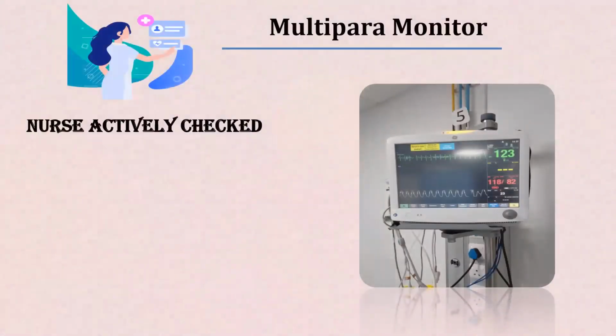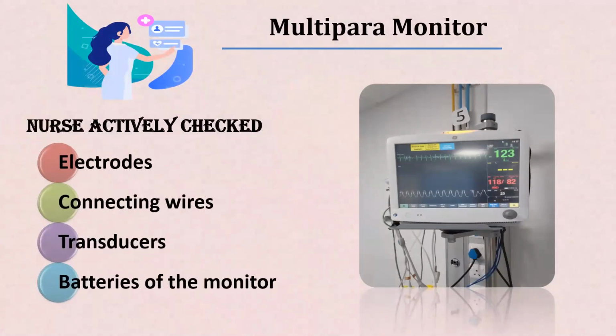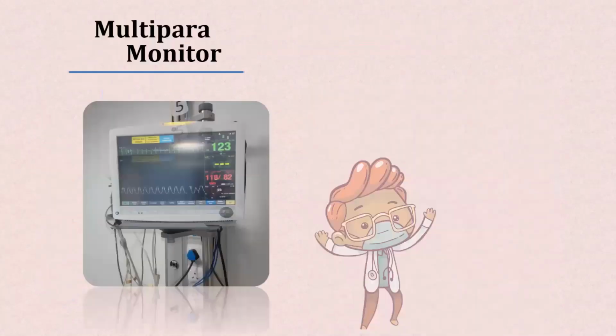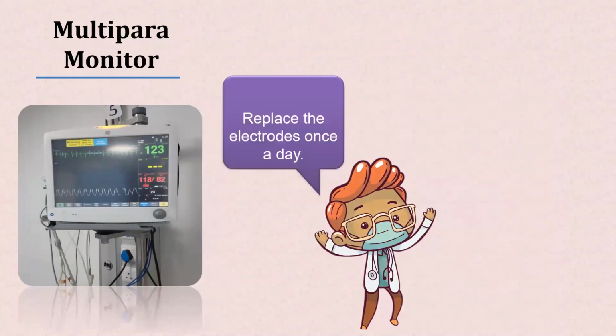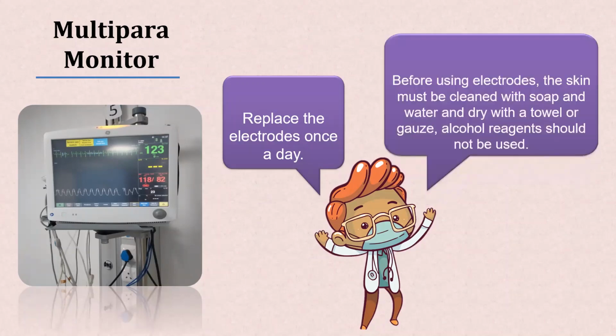As you can see in this picture, the multipara monitor. For the multipara monitor, the nurse actively checks the electrodes, connecting wires, transducers, and batteries of the monitor to determine their condition and integrity once a day. The duty nurse should replace the electrodes once a day, and before using electrodes, the skin must be cleaned with soap and water and dried with a towel or gauze. Alcohol reagents should not be used as these reagents are irritant and damage the patient's skin.